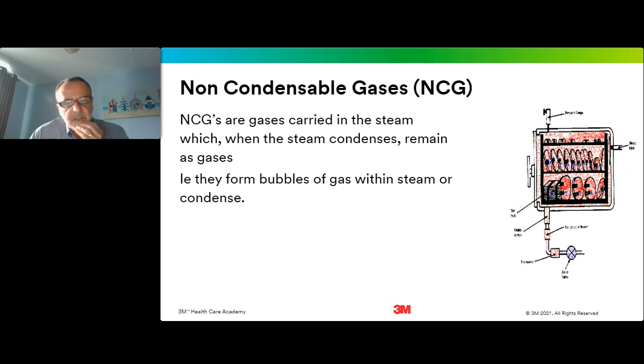So let's consider non-condensable gases, because although these in themselves are not dissolved contaminants, they can be present in the steam and they can be carried into the chamber during the sterilization process. And if they are carried into the chamber, then if they're in sufficient quantity, as the steam condenses on the cold load items, you can get the formation of pockets of non-condensable gas within the load, which will prevent the action of steam on the microorganisms and therefore potentially a non-sterile load.